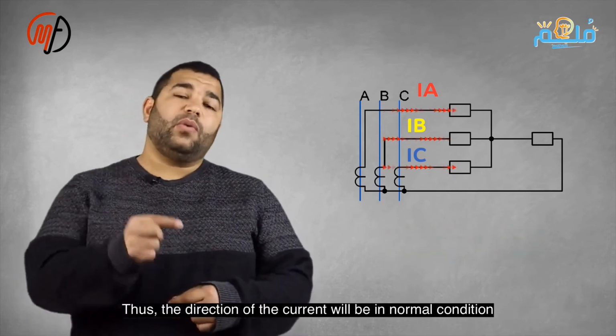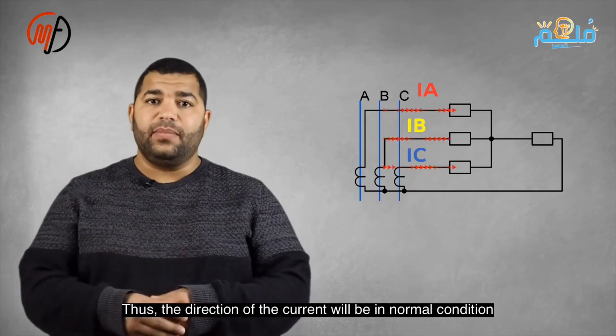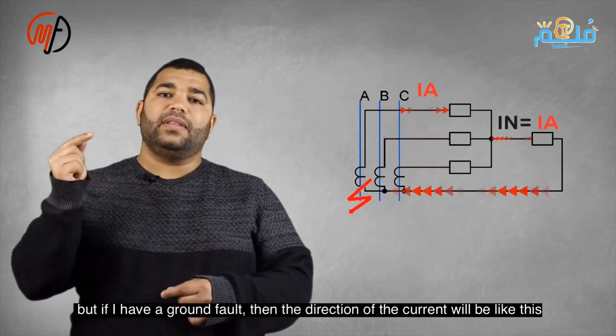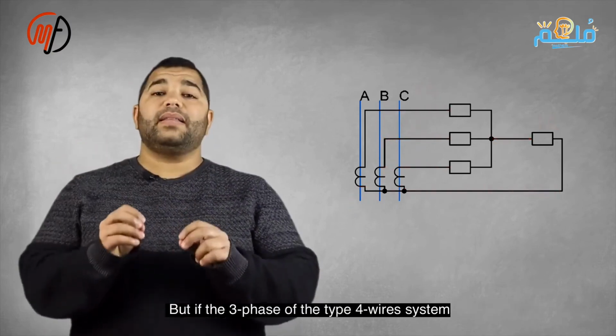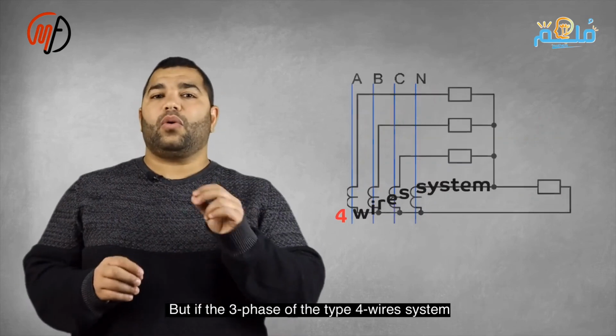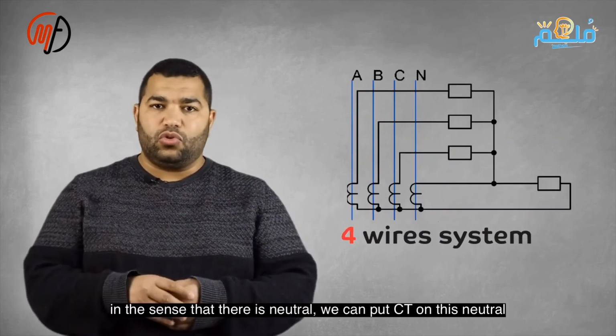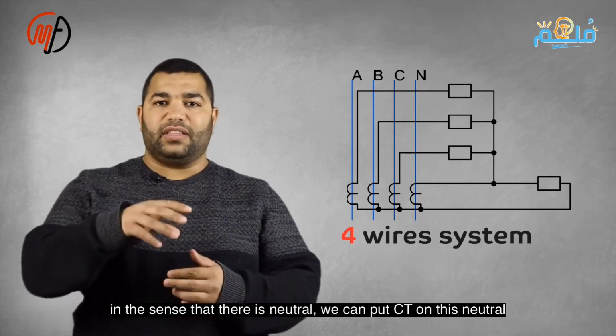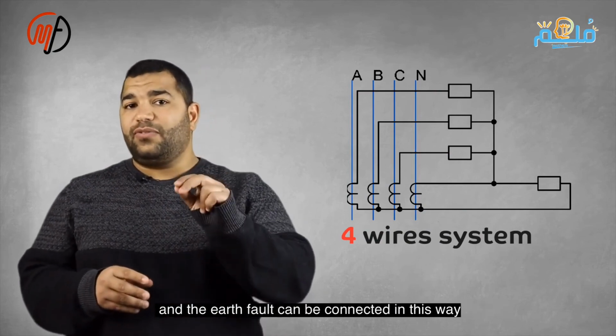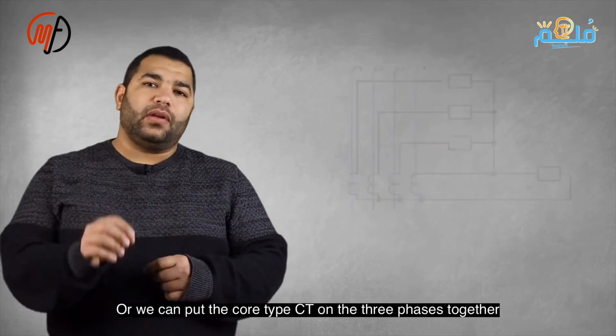In a three-phase four-wire system, a CT can be on the neutral. A core-type CT detects ground faults, called a sensitive earth fault; or one CT on the neutral. This means if there is a neutral, place a CT on the neutral to connect the earth fault, or use a core-type CT on all phases for sensitive earth fault detection.